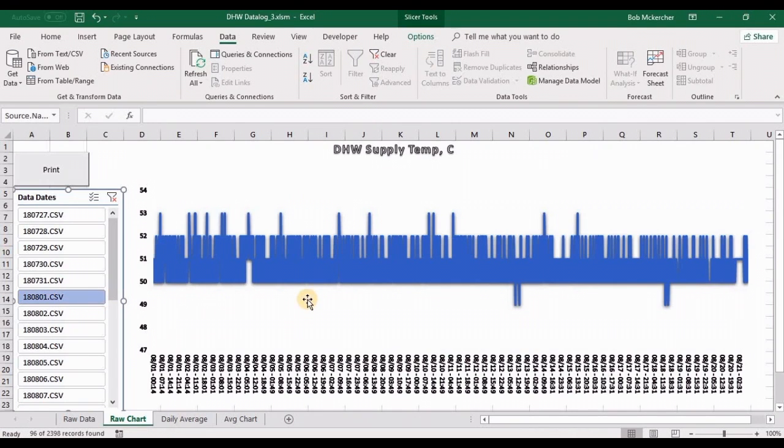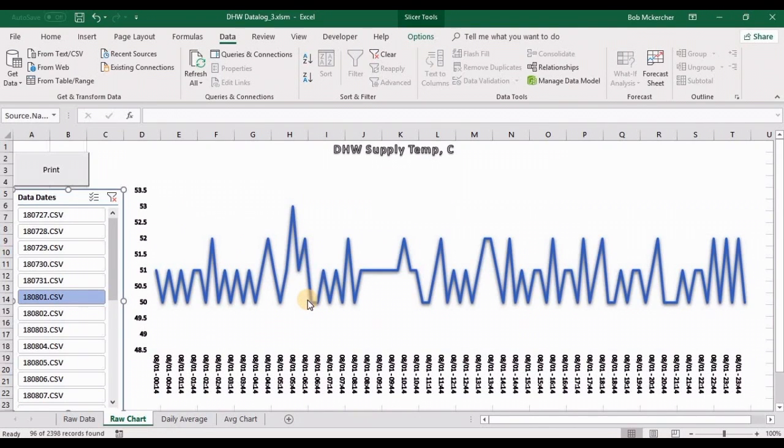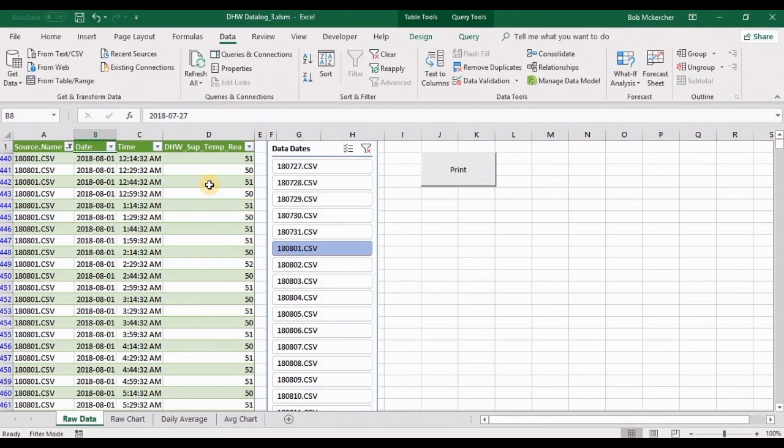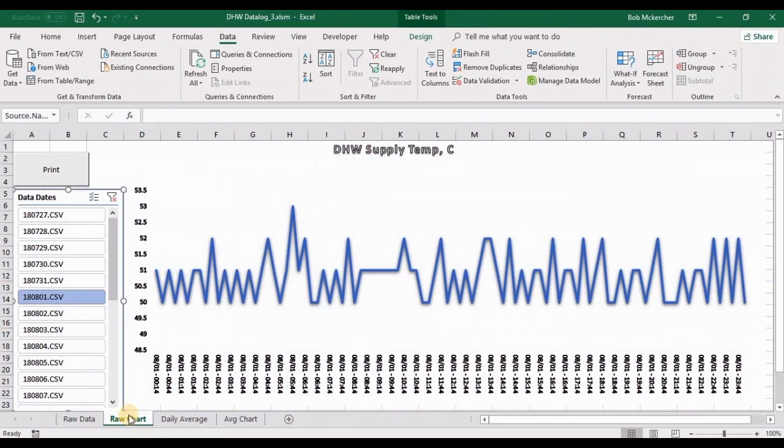One thing of note is that when we download new programs onto the PLC, during that period, the PLC essentially isn't looking for temperatures. So if a data log is triggered at the same time that we're downloading a program, the value that will be recorded will be 0. And it will look something like this.